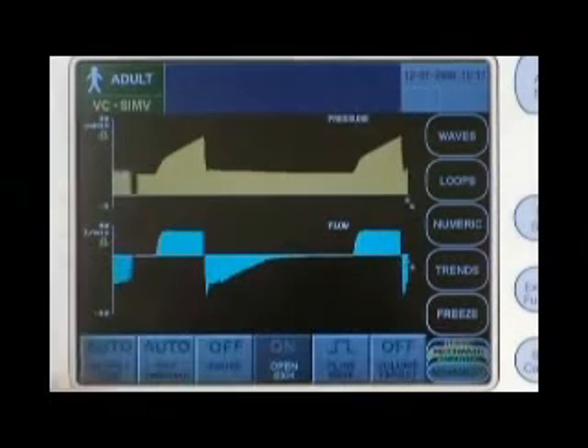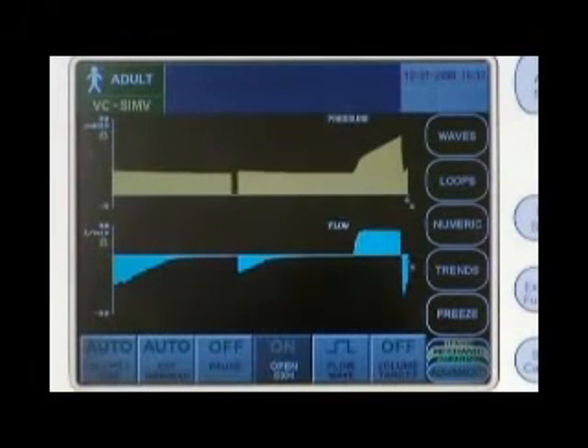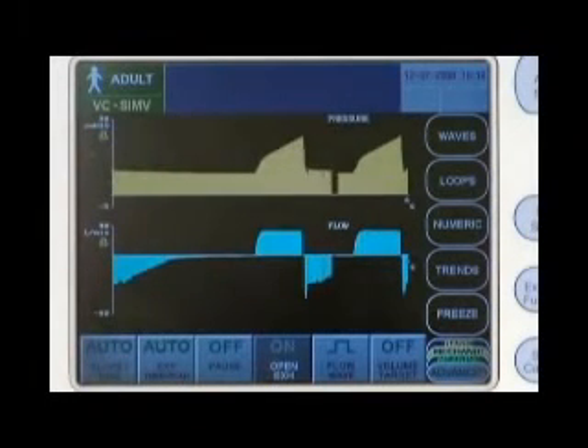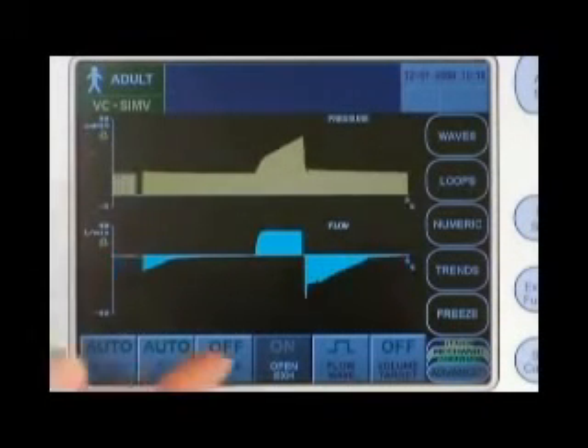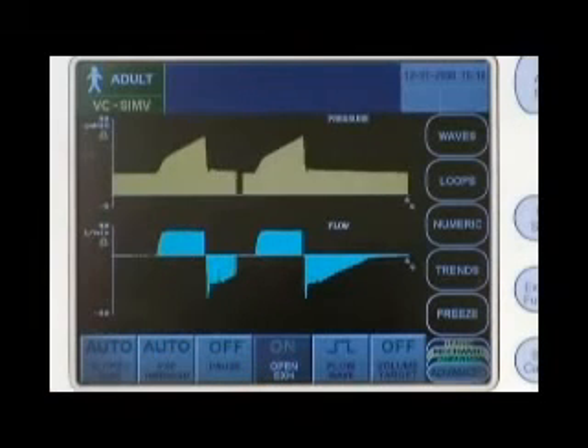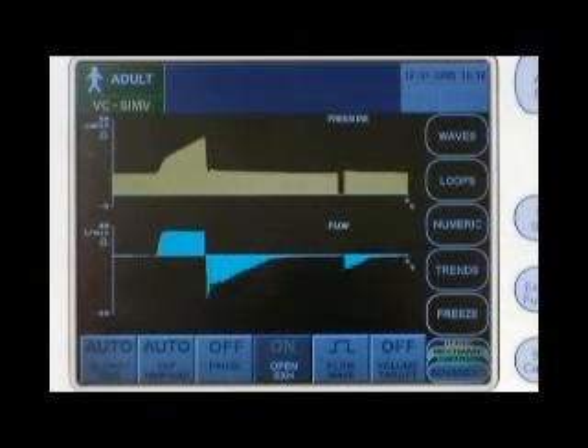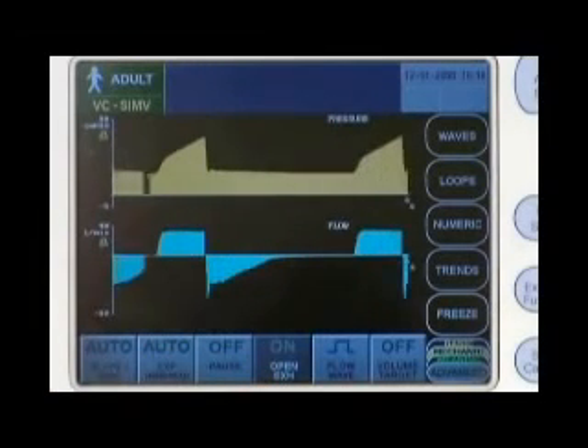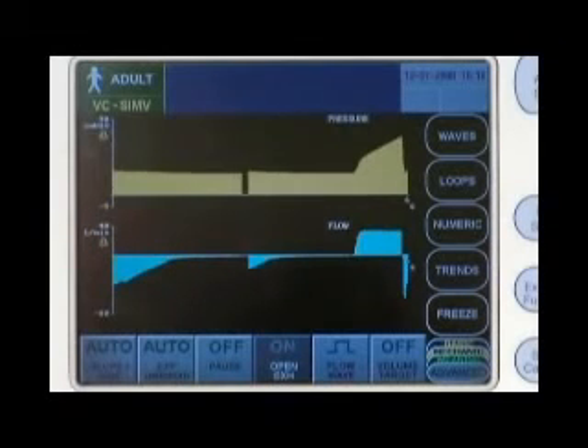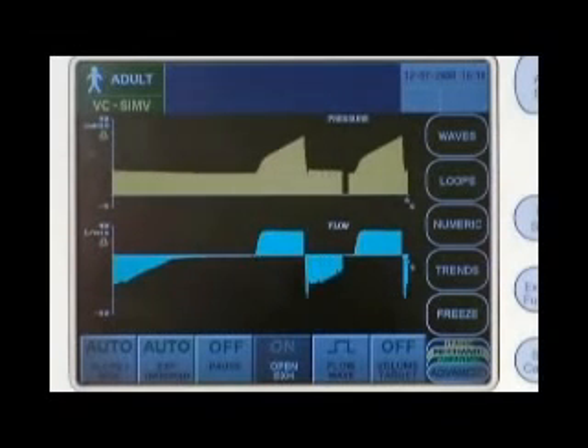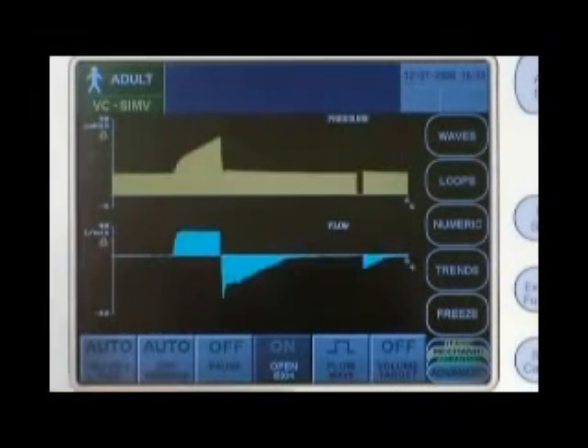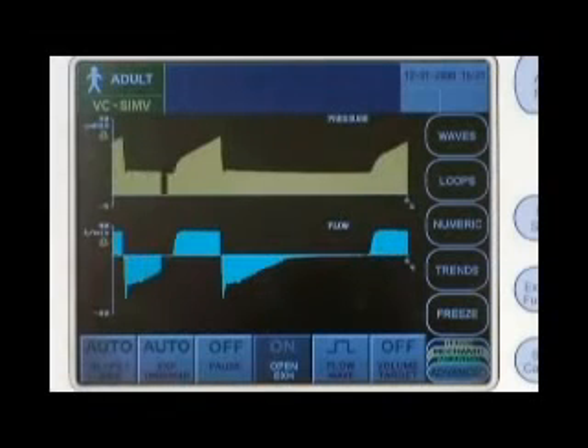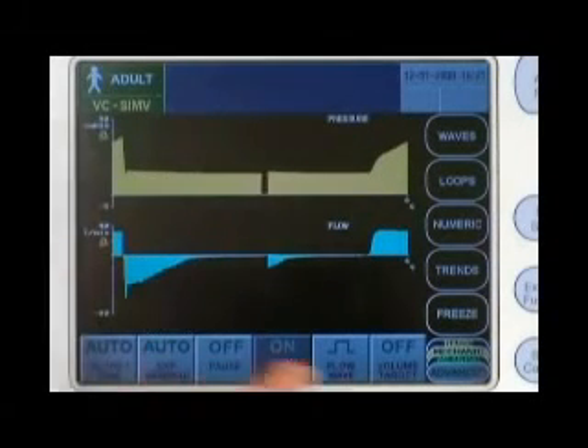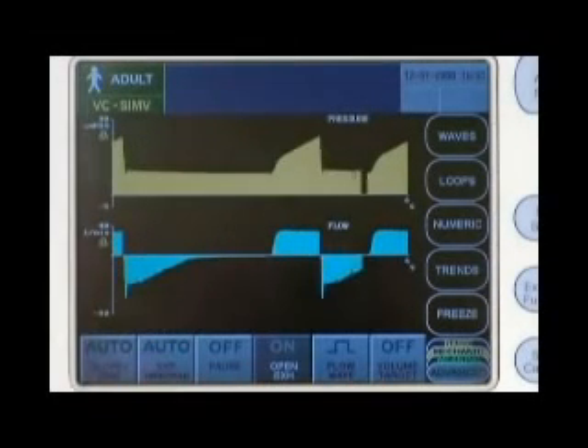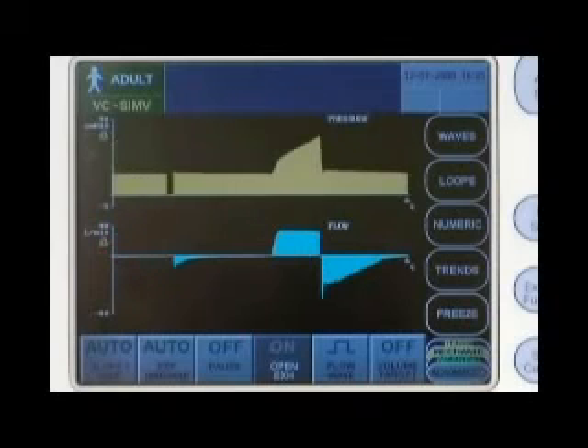The advanced data set parameters are touch active. This is where you adjust slope rise, expiratory threshold, pause, and flow waveform settings. It is also where you activate the 2 advanced breath types, biphasic pressure release ventilation and volume target pressure control ventilation. The open exhalation button activates biphasic pressure release breath type, and the volume target button activates volume target pressure control breath type.